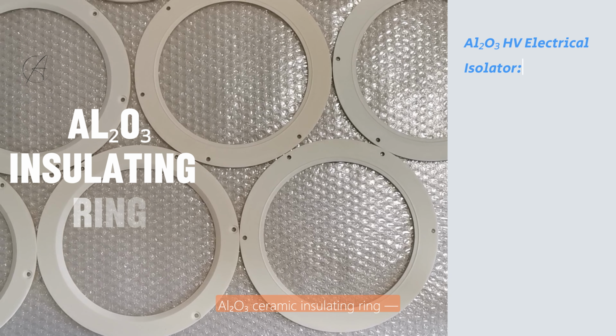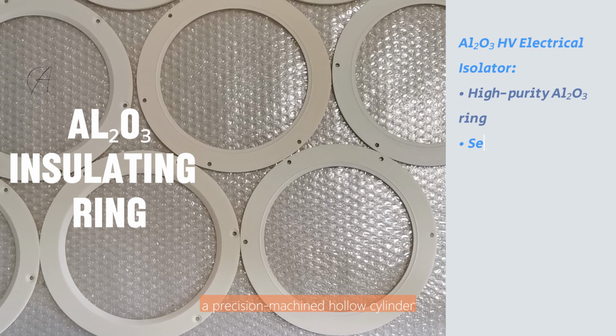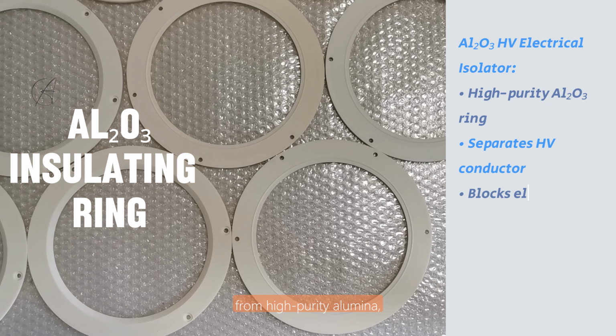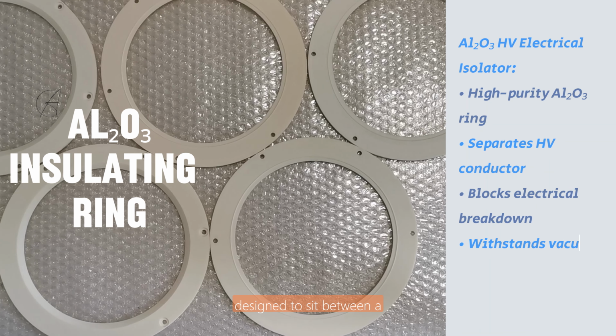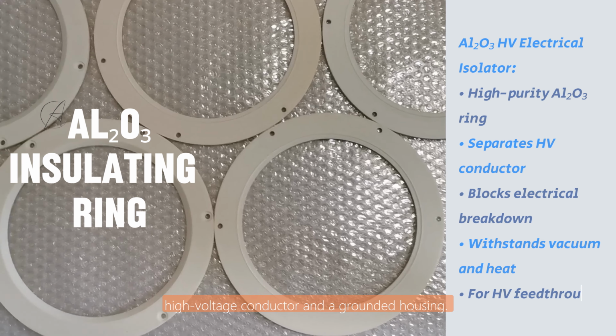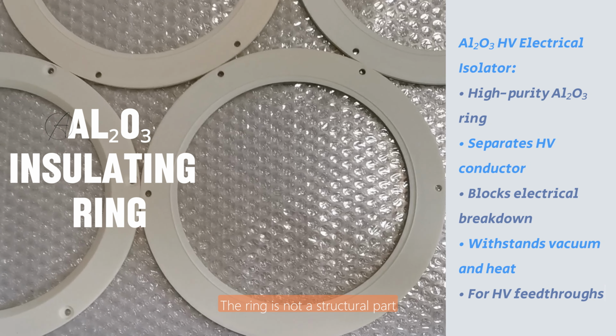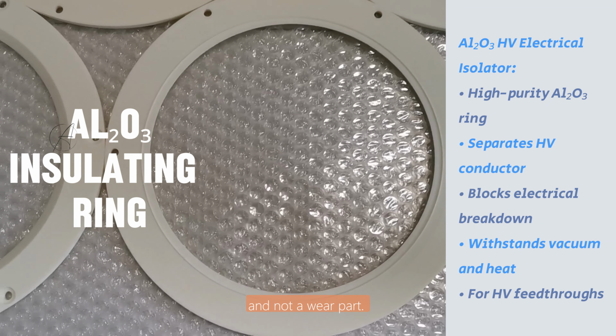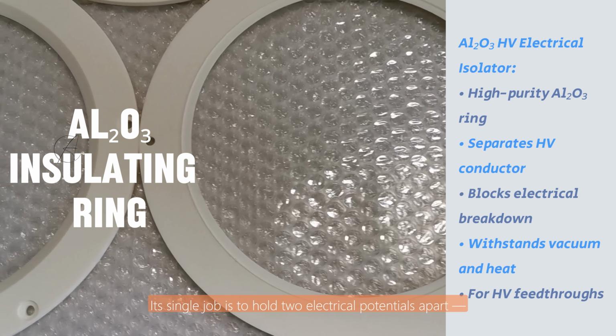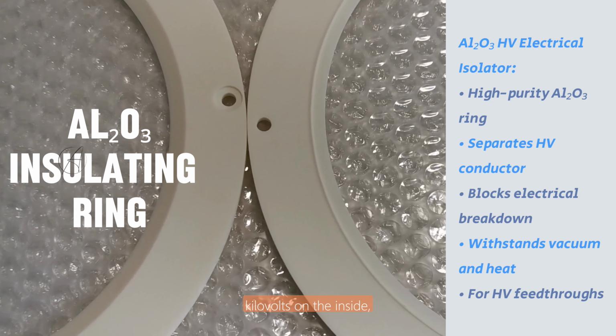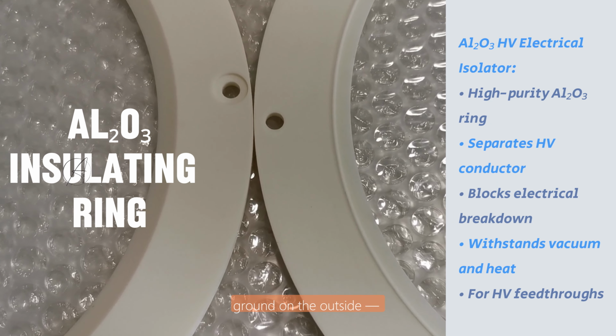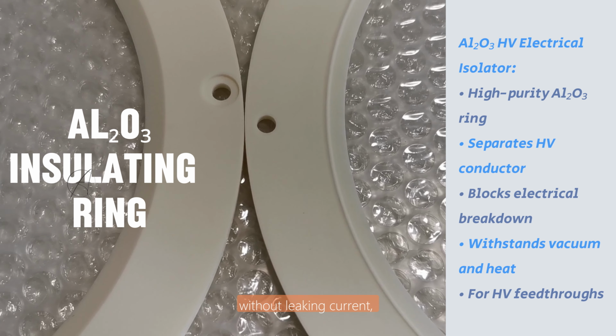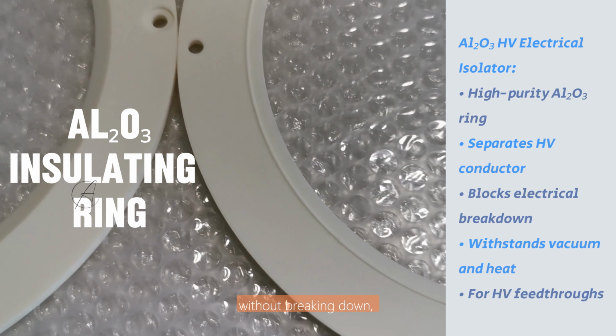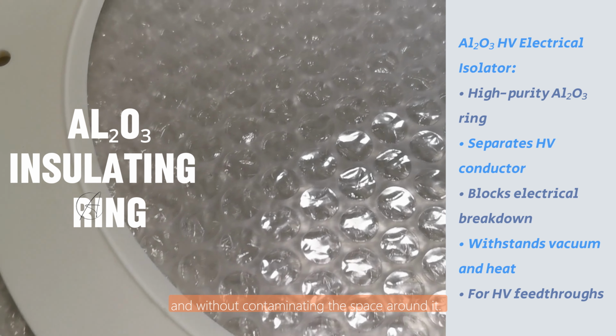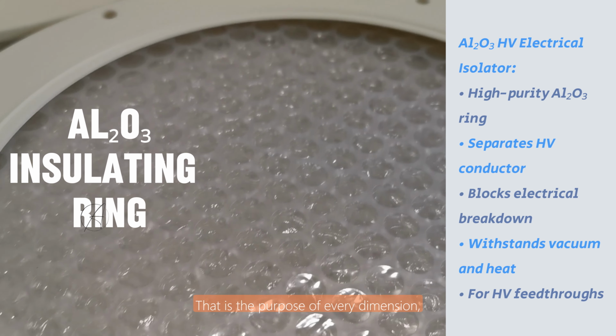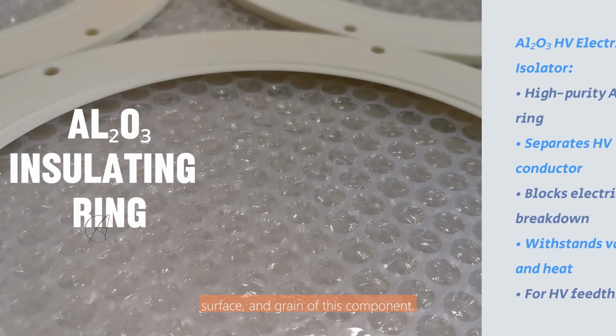Aluminum oxide ceramic insulating ring, a precision machined hollow cylinder from high-purity alumina, designed to sit between a high-voltage conductor and a grounded housing. The ring is not a structural part and not a wear part. Its single job is to hold two electrical potentials apart, kilovolts on the inside, ground on the outside, without leaking current, without breaking down, and without contaminating the space around it. That is the purpose of every dimension, surface, and grain of this component.